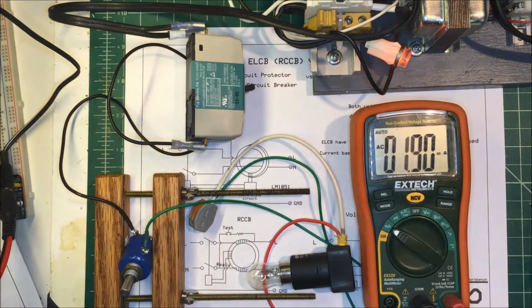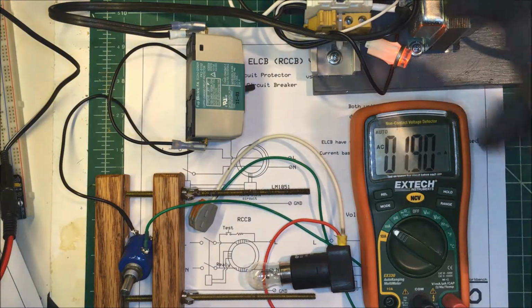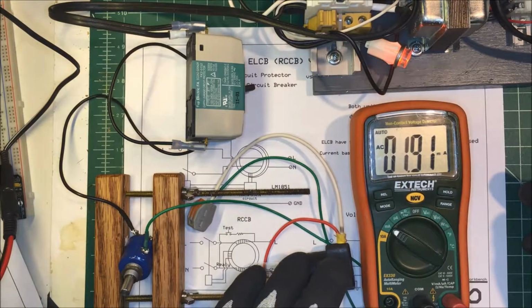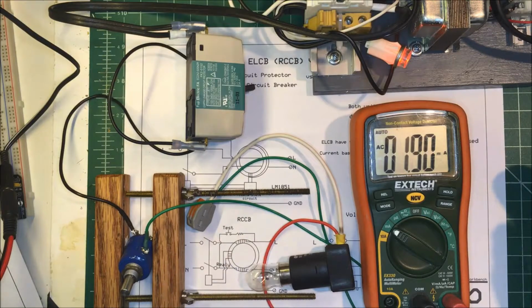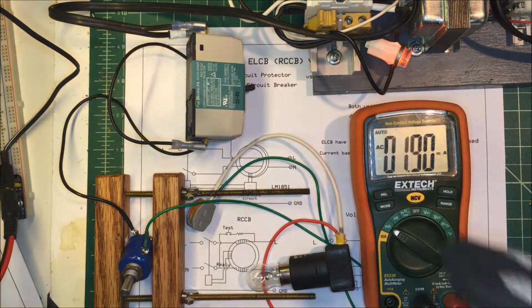And we're going to test this one, see how it works with the circuit breaker right here. I do have a couple of 50 milliamp fuses in line here, and I have a lamp here just so it doesn't draw too much current if something goes wrong. And I have my eye protection on, and I'm standing on a rubber mat right now. So right now we have 0.19 milliamps running through the breaker to ground.